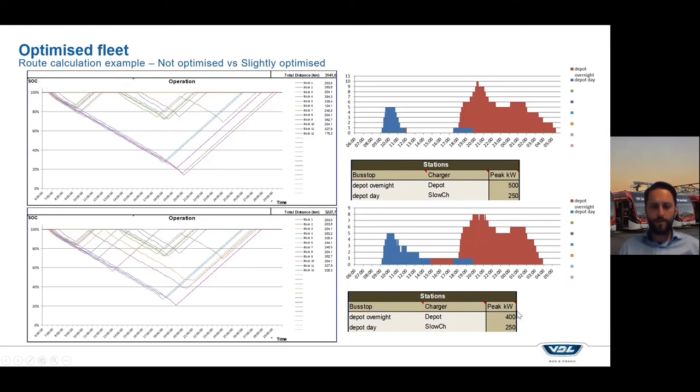A different thing to notice that's really important for customers is the peak that you need on the energy, on the grid connection. This is only 12 buses, so it's not too much, but still we reduced from 500 to 400. If you can spread out this charging peak a bit more, only go to five, then you might even need only 250 kilowatts at the same time on your depot.